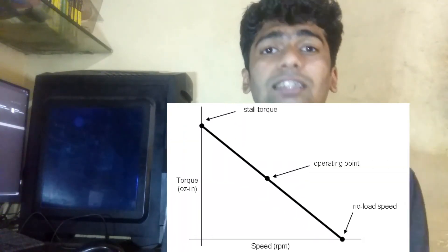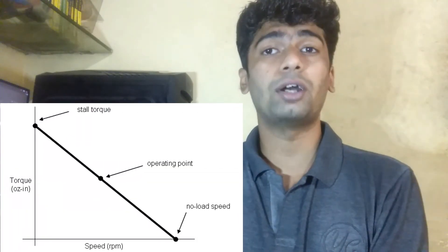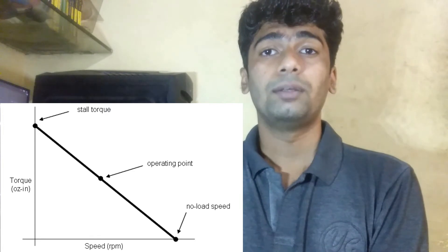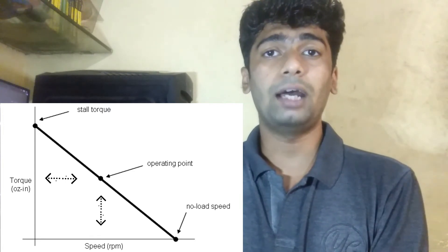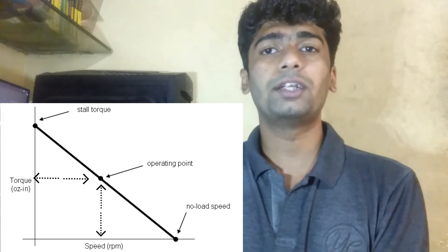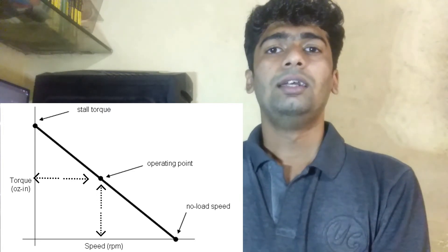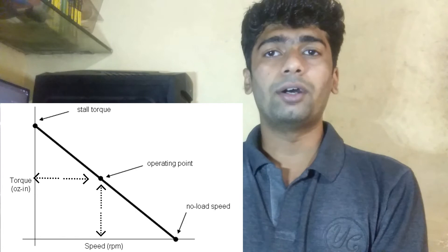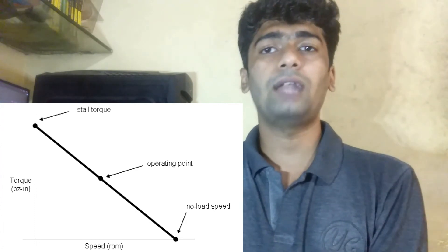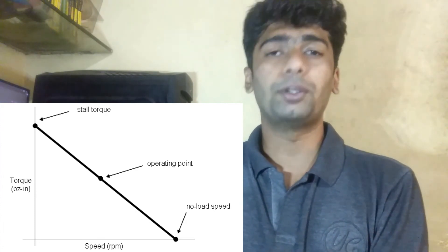We can also understand Stall Torque as the torque required to stop the motor's shaft from rotating. Whereas the Rated Torque is the maximum continuous torque that the motor produces at the rated RPM, when working normally and without overheating — it is the operating torque we would like to operate at for a particular application.